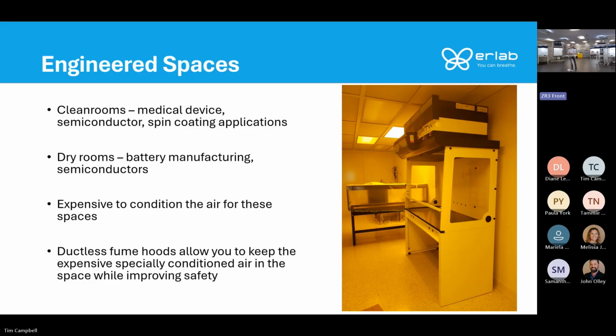So if you have to use chemicals, you're probably using them on the open bench. You're not putting a ducted hood in there because that's going to go against the airflow of all that clean air. Well, with our ductless fume hoods, you can put our HEPA filter on the exhaust side of the carbon filtration. It helps you keep that particle integrity count of the clean room, but then allows you to safely use the chemicals you're using, whether it's a spin coating application or say it's a medical device and you're using solvents.